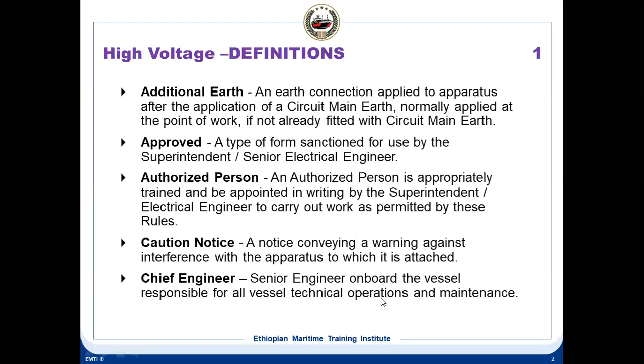Caution notice means a notice conveying a warning against interference. I will show you this additional earth in the practicals. We have to make two types of earthing: one on the breaker, then an additional earth using portable earthing cables. I will show you in practice how we make this additional earth, especially bus bar earthing. It is in addition to the main earth or circuit earth. A caution notice is just a notice warning against interference with the apparatus to which it is attached.